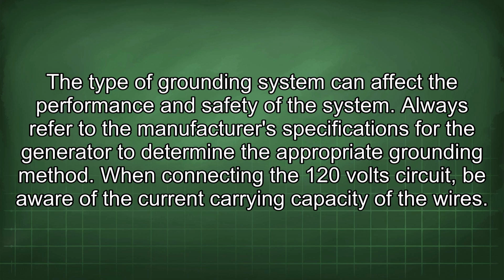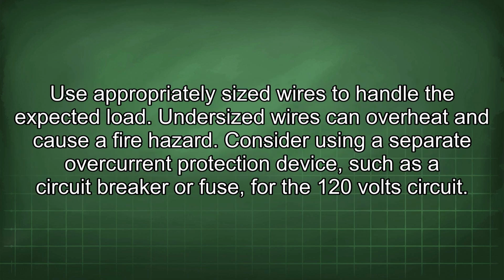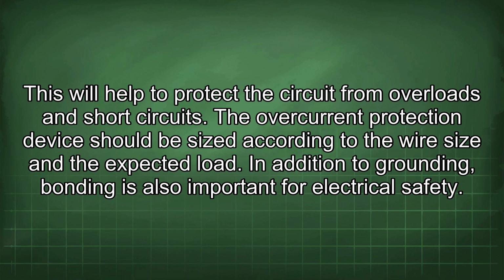When connecting the 120 volt circuit, be aware of the current carrying capacity of the wires. Use appropriately sized wires to handle the expected load. Undersized wires can overheat and cause a fire hazard. Consider using a separate overcurrent protection device such as a circuit breaker or fuse for the 120 volt circuit. This will help to protect the circuit from overloads and short circuits. The overcurrent protection device should be sized according to the wire size and the expected load.